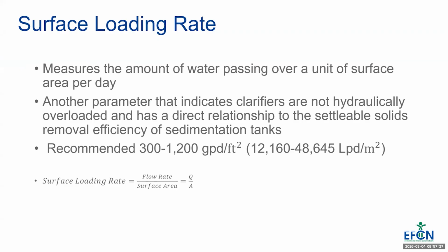The next topic is surface loading rate. And so this measures the amount of water passing over a unit of a surface area per day. So this is another parameter that indicates your clarifiers are not hydraulically overloaded. It has another direct relationship to your settlable solids and your removal efficiency of your sedimentation tanks.